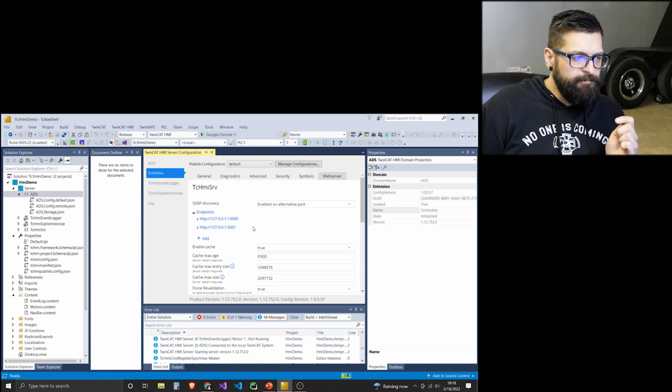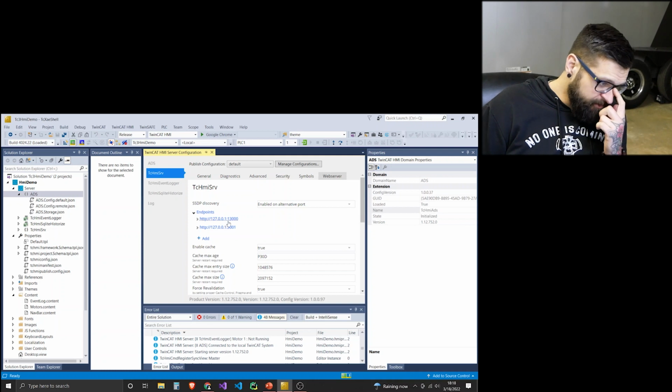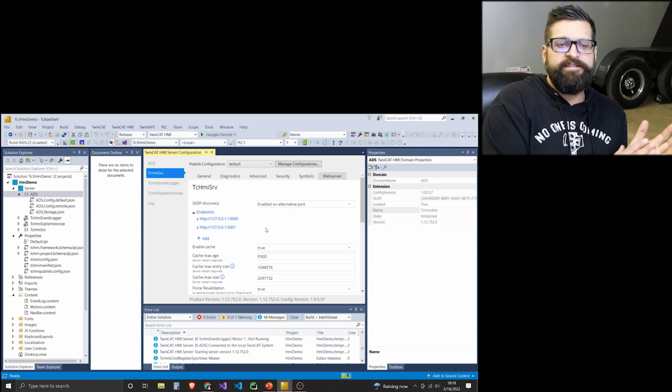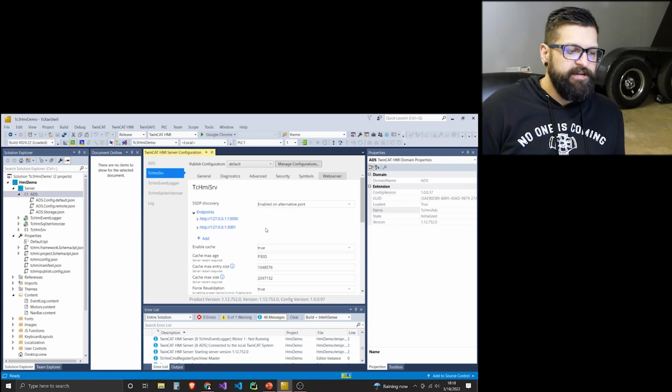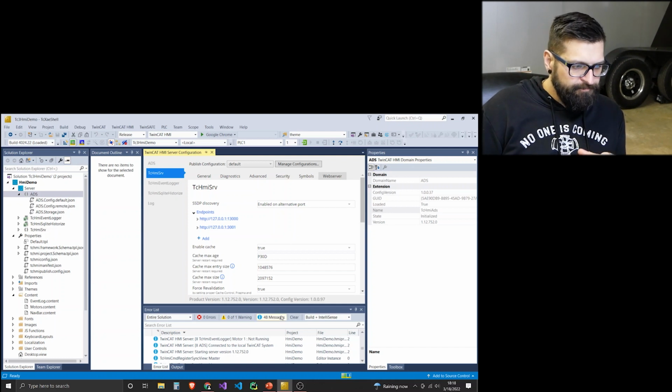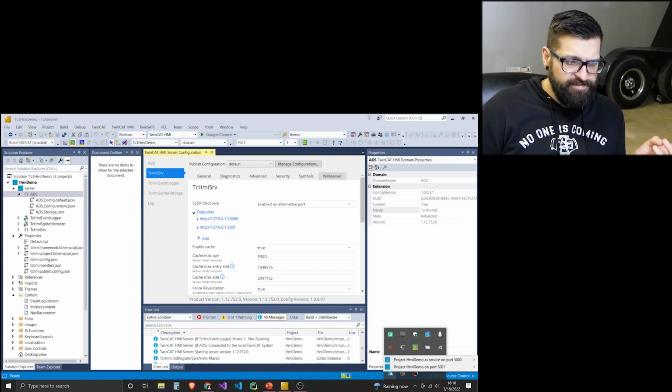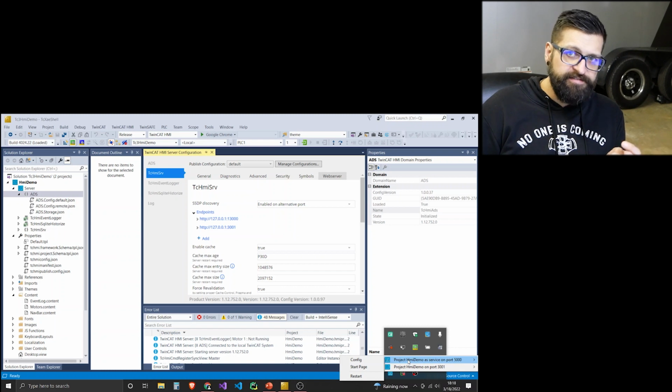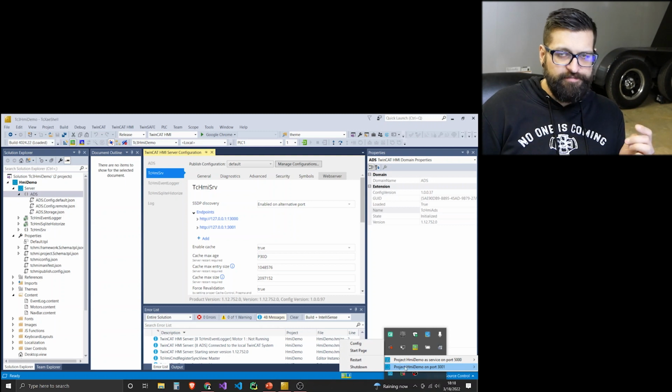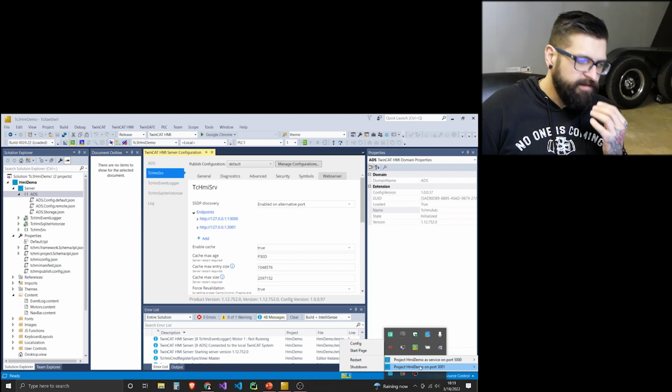And these are just set up because I've installed multiple. I have both the engineering environment and the TF2000 installed on my computer. So if you look down in the lower right-hand corner, you can see that I've got two web servers actually running. I'm publishing to 5000, so that's what I'm treating as the TF2000 production web server. And then this is my engineering server down here, port 3001. That's my live view. So my engineering server, when we get into it later and you see the live view, is the server that is being called for displaying my HMI in real time as I work on it.